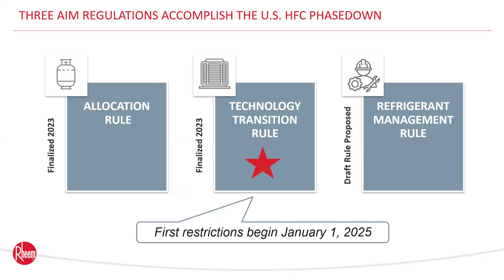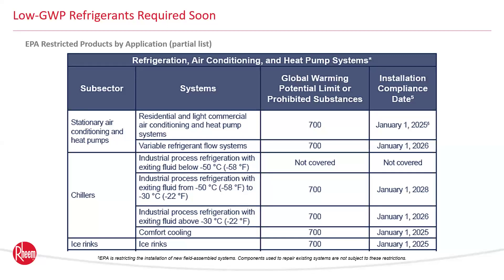Our main focus is the second leg of the stool: the transition to substitutes through GWP limits for specific applications. The EPA technology transitions rule is now final, and starting as soon as January 1st of next year, GWP restrictions will take effect in new refrigeration, air conditioning, and heat pump equipment. For stationary air conditioning, heat pumps, and chillers for comfort cooling, the prohibition on substances higher than 700 GWP is as early as 2025.